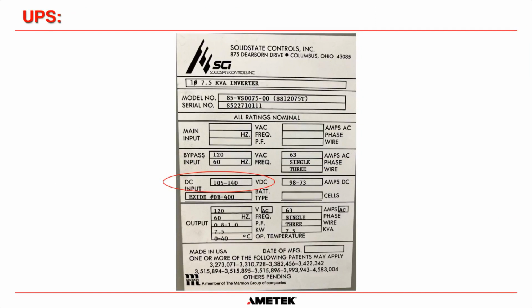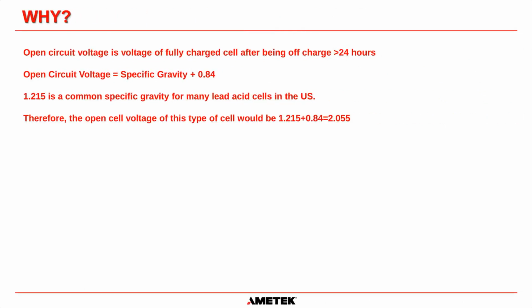And for a UPS, this is the rating plate for one of our inverters, a 7.5 kVA inverter. And we stipulate that the DC input into that inverter must be between 105 and 140 volts DC for it to work correctly. So that is why we use 60 cells in lead acid, and why those voltage tolerances are there: all the load circuits that are connected to the DC will have some form of tolerance that we have to adhere to.